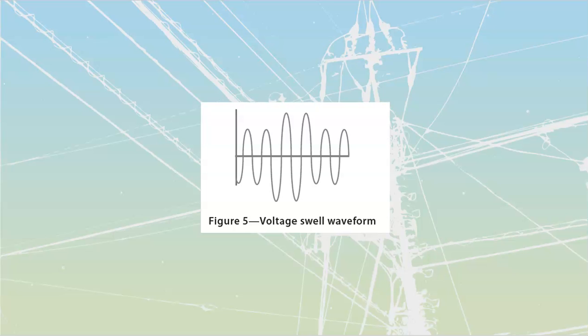A voltage swell is going to be a large amount of voltage that happens for a short amount of time. Overvoltage is too much voltage for a long period of time, over a minute. A swell, or what we commonly call a surge, is anywhere from 110 to 180% for a short amount of time, from half a cycle up to a minute. All sorts of things can cause it.